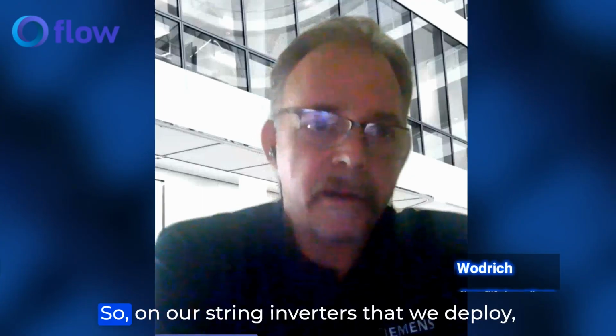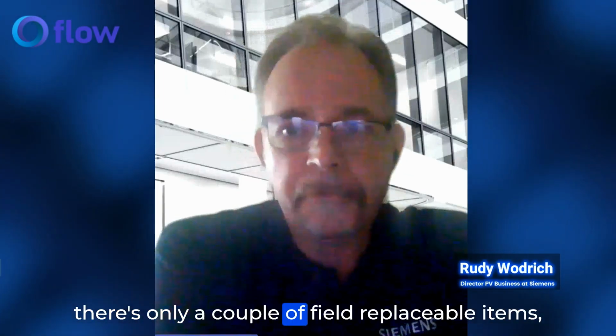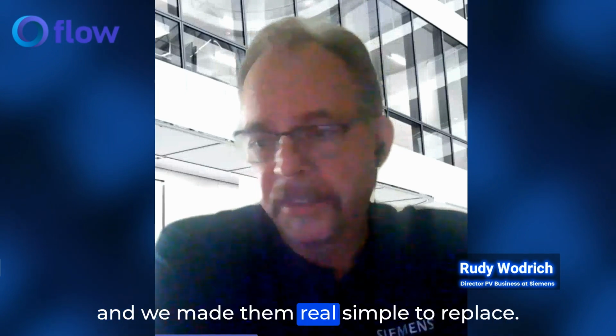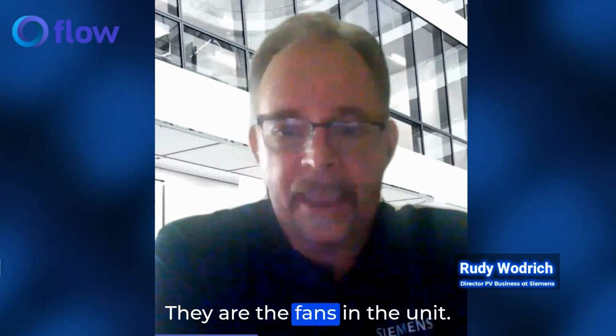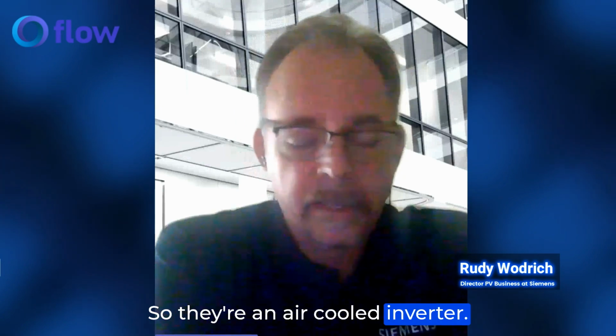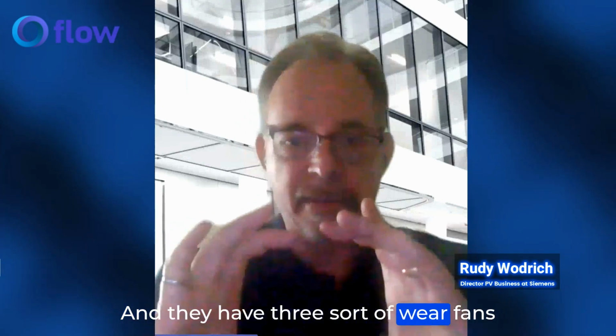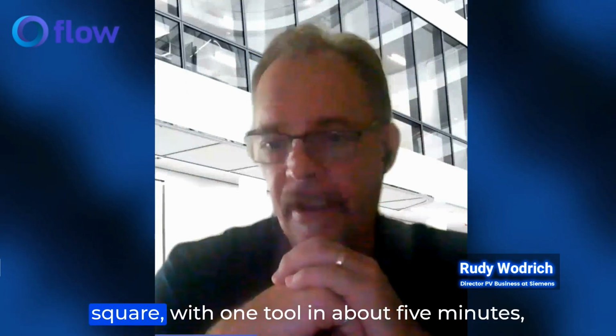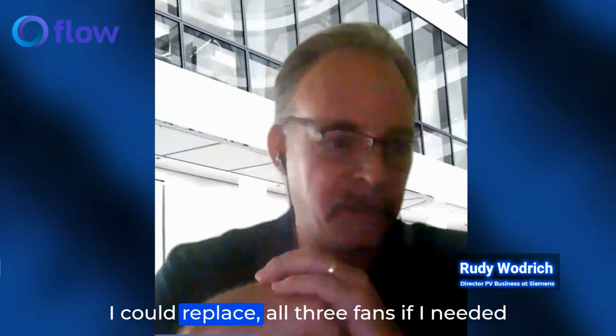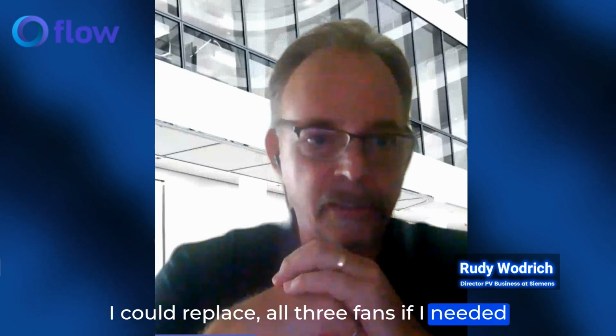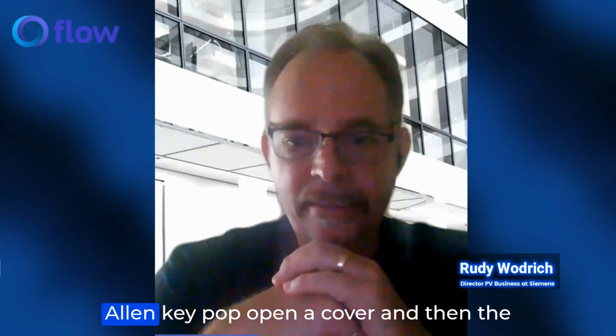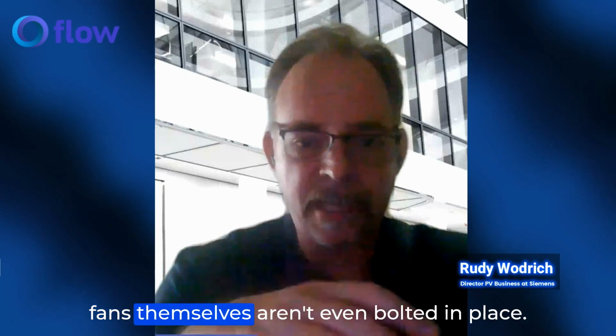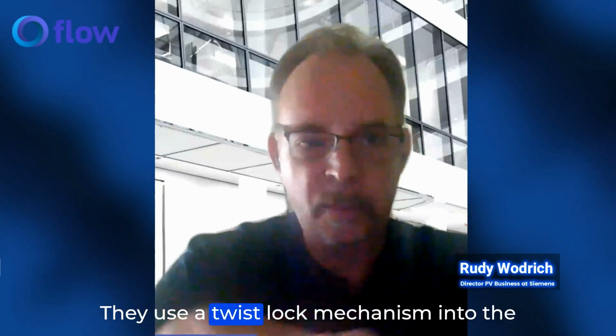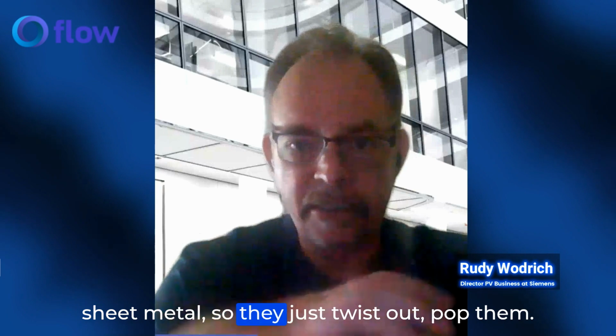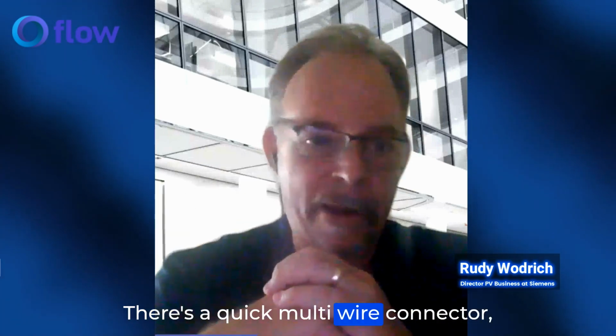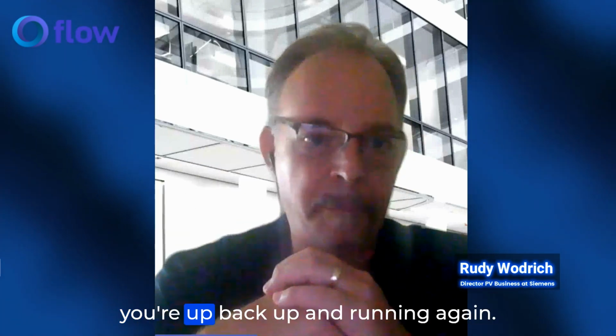On our string inverters that we deploy, there's only a couple of field replaceable items, and we made them real simple to replace. They are the fans in the unit—it's an air-cooled inverter with 3 square fans, about 4 inches square. With one tool, in about 5 minutes, I could replace all 3 fans if there was a failure. Basically it's an Allen key, pop open a cover, and the fans themselves aren't even bolted in place—they use a twist lock mechanism into the sheet metal. So they just twist out, pop them, there's a quick multi-wire connector, and you snap a new one in—boom, you're back up and running again.